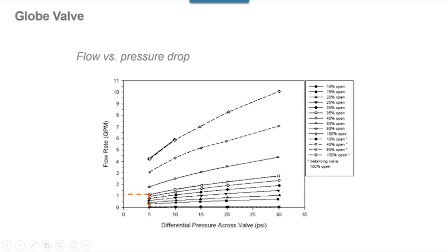But notice what happens, and I'm going to focus on this 40% open line. Each of these lines represents the valve being locked open at a certain percentage. And if I focus on this 40% line, because that's a very common area, you're going to see a modulating control valve, primarily controlling in that 0 to 50% range once you get up to temperature in the morning. If we increase that pressure across the valve to 10 pounds, look what happens to my flow. I basically pick up about a half a gallon.